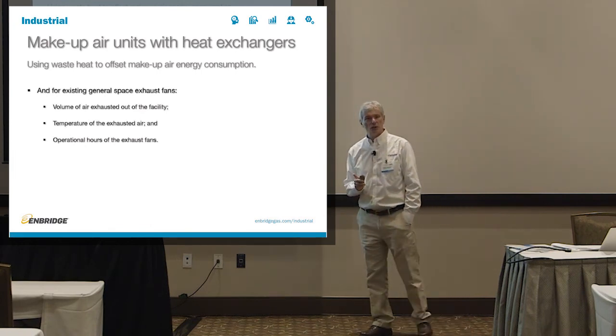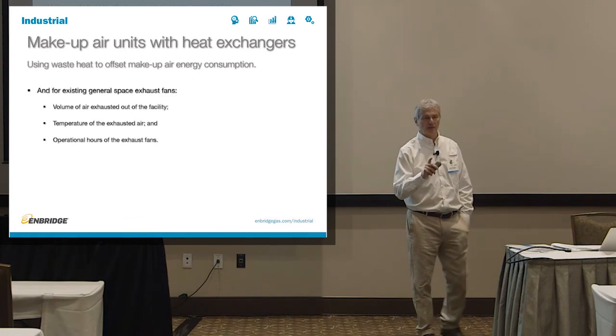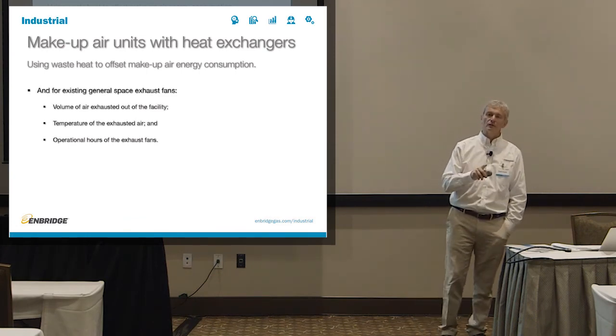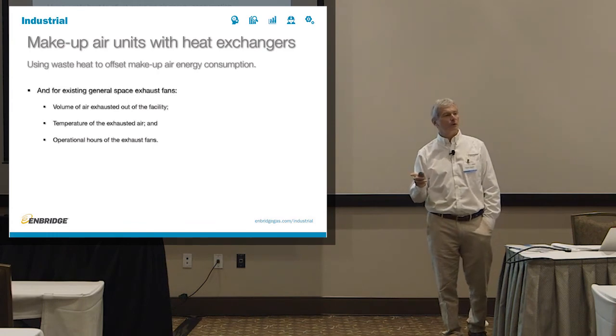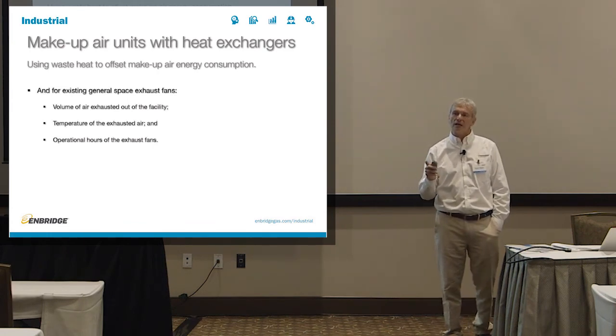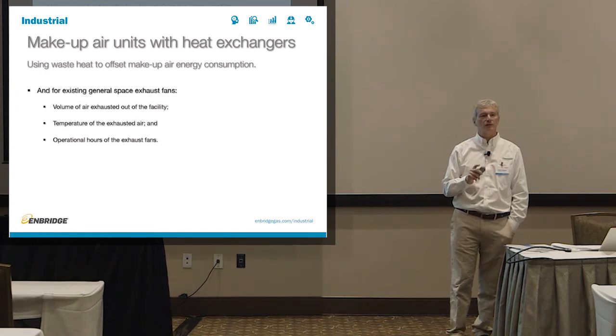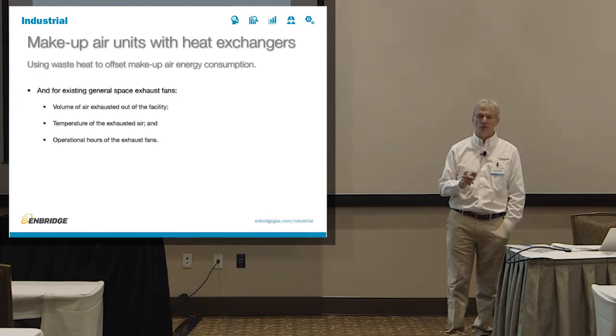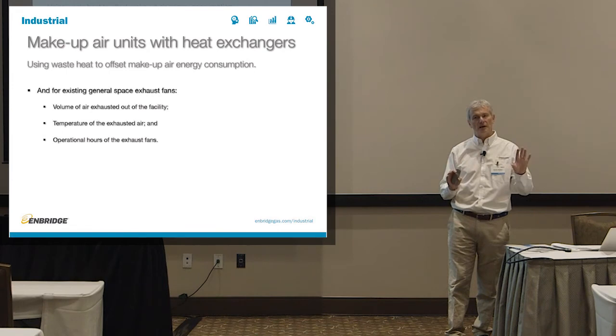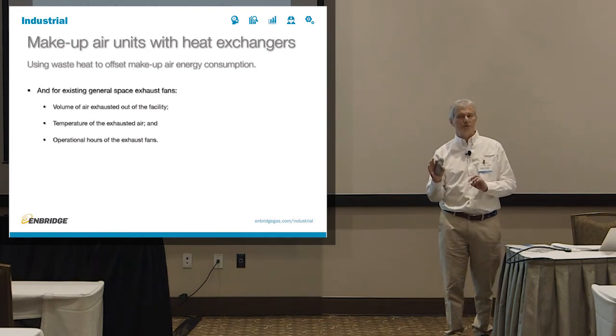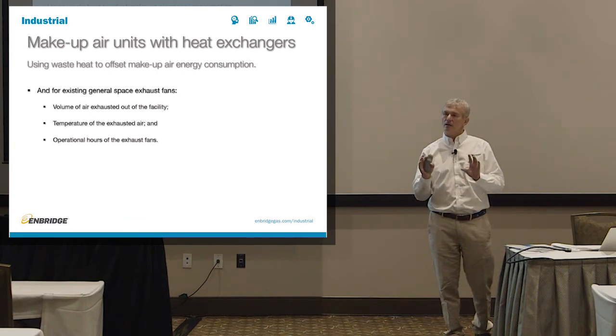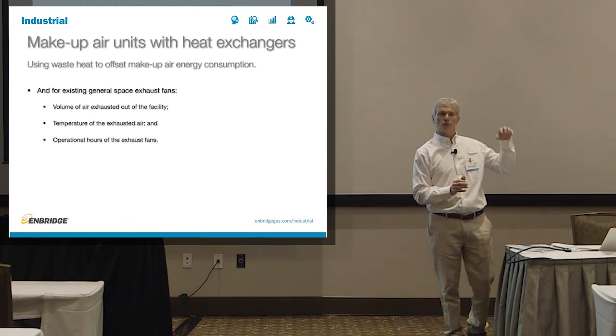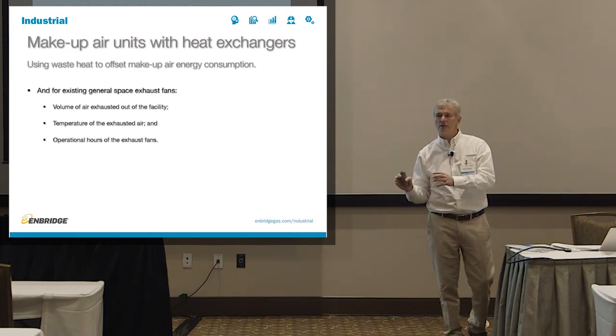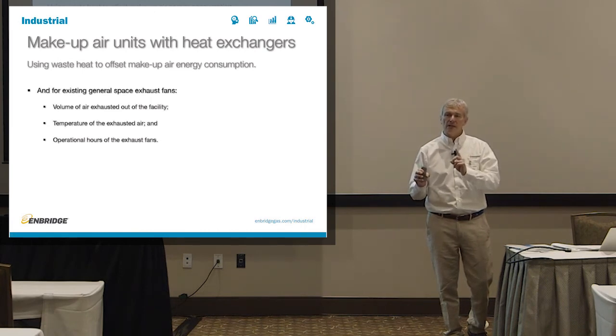So for space exhaust fans, I mentioned it's really important to have the balanced facility. Because if you have 10,000 CFM of makeup air and 100,000 CFM of exhaust, you will generate such imbalance in your facility that no amount of energy savings will help you. You will still waste all of that energy. Step number one is to have corresponding numbers of CFM of air coming into the facility and CFM of air coming out of the facility. And again, in the majority of the cases, people will gravitate towards buying more makeup air and keeping exhaust where it is. And for only one out of 10 of you, that will actually be the right solution.